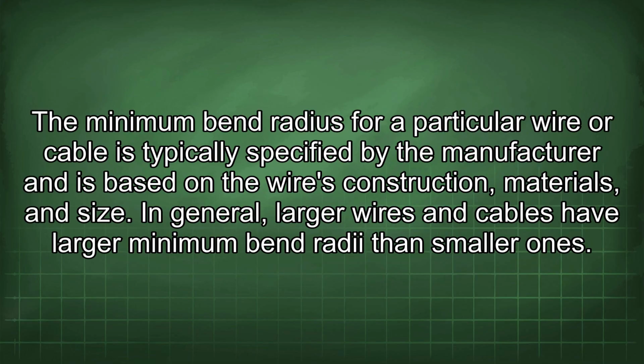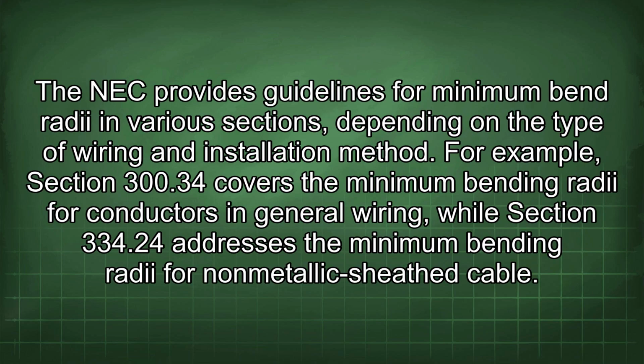The minimum bend radius for a particular wire or cable is typically specified by the manufacturer and is based on the wire's construction, materials, and size. In general, larger wires and cables have larger minimum bend radii than smaller ones. The NEC provides guidelines for minimum bend radii in various sections depending on the type of wiring and installation method. For example, Section 300.34 covers the minimum bending radii for conductors in general wiring, while Section 334.24 addresses the minimum bending radii for non-metallic sheath cable.